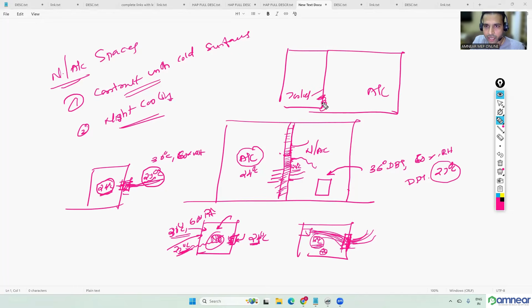Most of the time, people complain about this. Suppose you have a toilet area and another air conditioned area, and people are always complaining near the door area. People enter from the toilet area to the inside, and there is a partition between the toilet and the air conditioned space. On that partition area we will have a condensation issue. The reason is infiltration, because the toilet is not an air conditioned space.